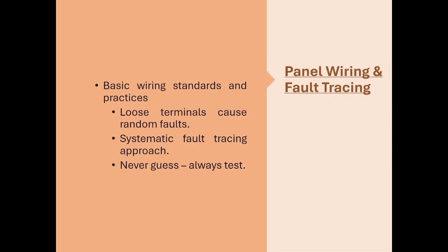Okay? And that takes us to panel wiring and fault tracing. So let me bring this closer to real site experience. Panel wiring is where many automation problems begin. When we talk about wiring, we mean how cables are terminated, labeled, routed, and secured inside panels. Loose terminals, poor labeling, and bad workmanship create faults that appear and disappear. Fault tracing, like I said, simply means following a signal step by step until you find where it is lost. And good fault tracing is systematic. You don't guess, you test, you confirm, and you move logically.